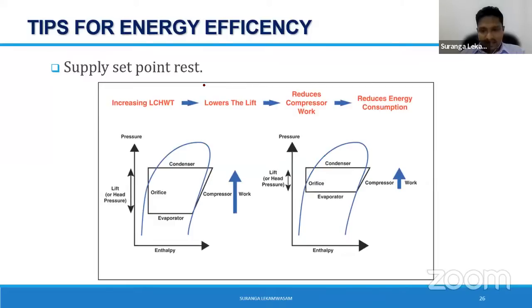With that, I will touch on a few energy saving tips, or rather energy efficiency improvement tips, which are again very essential. I'll quickly run through. Supply set point reset. In a typical chilled water system, we run our chilled water supply at around 7 and get the return at 12, if you refer to the conventional design. What will happen if your building load is less now? Your chilled water return is not 12. It will be less than that, maybe 10 or maybe 9, right? If the return temperature is less than the design point, you can give a program so that it checks for 10 to 20 minutes and gives an automatic reset to the chilled water supply set point.